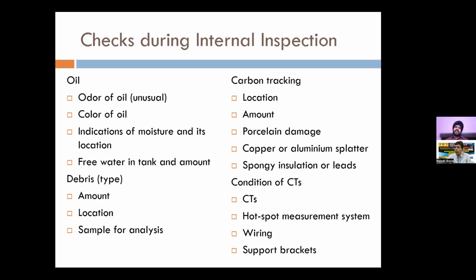Because recently at one of the failures at one of our stations, when we first entered that particular reactor, we first saw one spot of tracking. So that was the cold point of the tracking. So the flashover initiated from the corona shield, within the corona shield, so bushing base plate, and then later on we found two more spots. So there were three streamer arcs in that particular case.